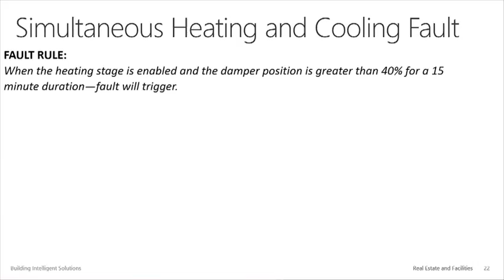So let's talk about a fault rule for simultaneous heating and cooling, meaning the mechanical system above us is providing the cool air. You could have half of it pushing hot air, half of it overcooling to compensate, and there's a battle going on up there, but we don't know it. That happens all the time.